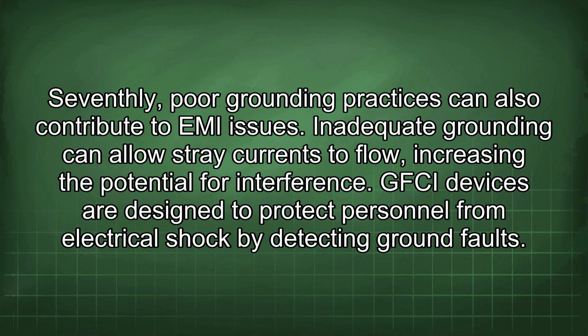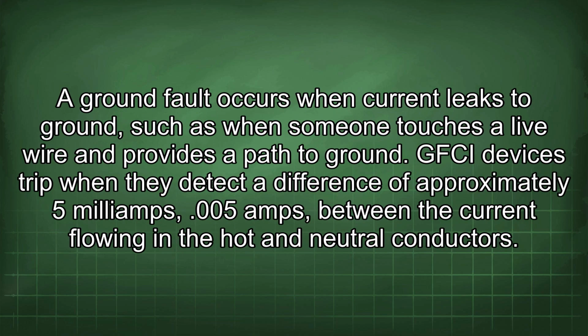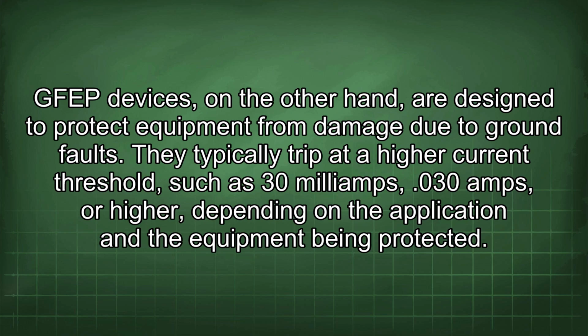GFCI devices are designed to protect personnel from electrical shock by detecting ground faults. A ground fault occurs when current leaks to ground, such as when someone touches a live wire and provides a path to ground. GFCI devices trip when they detect a difference of approximately 5 milliamps between the current flowing in the hot and neutral conductors. GFEP devices, on the other hand, are designed to protect equipment from damage due to ground faults. They typically trip at a higher current threshold, such as 30 milliamps or higher, depending on the application and the equipment being protected.